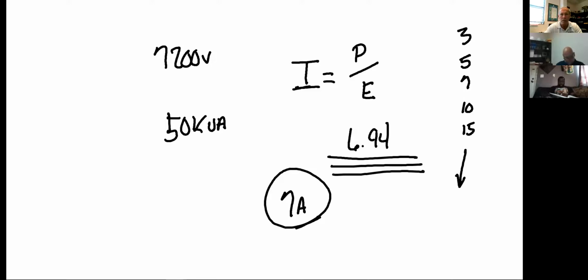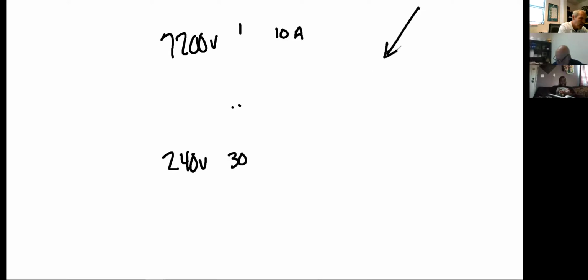Let's clear this screen. Primary voltage is 7,200. Secondary voltage is 240. Primary amps are 10. How many amps are on the secondary side? Do I need to figure ratio here? Yep, sure do. 7,200 divided by 240, 30. We're going down in our calculation. 300 amps. There you go. Perfect. Like I said, chat with us. You don't want to raise your hand or anything like that. Let us know if you've got any questions while we're going through this process.